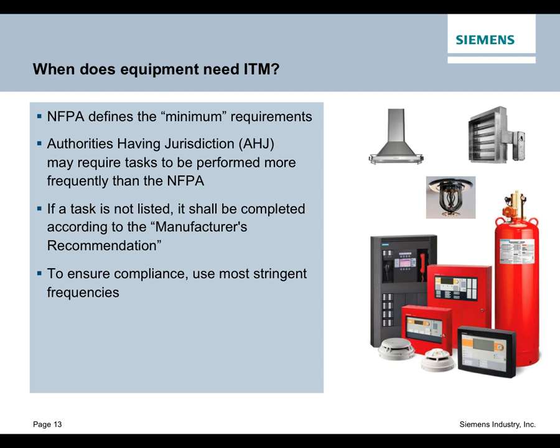So now we're going to touch base on when the equipment in your building needs to be inspected, tested, and maintained. And as I mentioned earlier, NFPA defines the things that they put in their code books as minimum requirements. But those authorities having jurisdiction, which could be your fire department, could be a governmental agency, ownership type of thing, the authority certainly can adjust that frequency. Once again, another part of what your trusted service advisor needs to be aware of and should be of a consultant nature to you. And there will be times where you may have a product in your building that does not show up in the code book. In that case, you always are pointed to follow the manufacturer's recommendations.